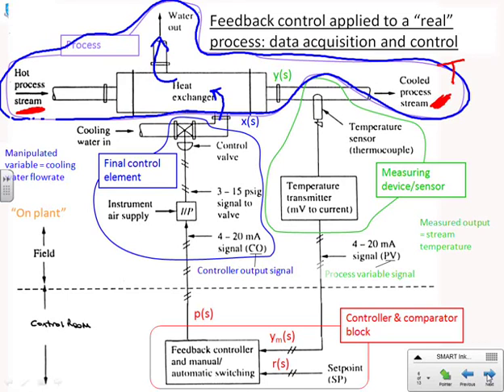So the question is how do I affect this cold flow? How do I affect the flow rate? If I now draw a red line around the actuation, we've got an actuator. I'm using this red loop to show you what's going on. You'll see I've got a control valve, essentially that's a bit like a tap. It's something that I can turn, and as I turn it affects the flow rate of cooling water going through the heat exchanger. Now how does this control valve actually turn? Well you'll notice in this particular case it's turned by an air supply, some high pressure air, and that's affected by some input signal U here. The key thing is we've got a signal coming in and that signal affects the flow rate of the cooling water. So that's the actuation.